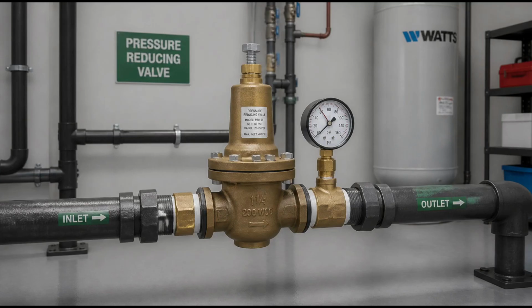Because RPZ assemblies and similar backflow prevention devices are so critical to public water safety, they are required by code in virtually every commercial building. And because their function depends on mechanical components remaining in good working order, they must be tested regularly by certified technicians. Testing involves isolating the device and applying controlled pressure changes to verify that each check valve seals properly and that the relief mechanism responds correctly.